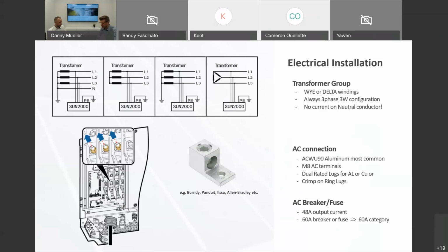Most people in the field use a TECK cable style cable to connect the inverter to their AC panels, and actually most people use an aluminum conductor, just from a cost savings perspective. That's the best bang for the buck. And in Canada, we have the ACWU90, which is the most commonly used. The terminal itself is an M8 stud for all of the three phases. You see them on the picture with those blue arrows and yellow nuts. And you can use either a crimp-on ring lug, or what most people do, use those dual-rated lugs, which are available from a multitude of manufacturers.